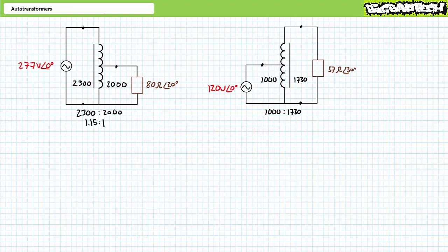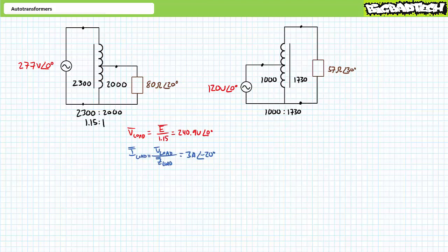Our first illustrated example features an autotransformer in a step-down configuration, where the larger primary input side has 2,300 turns, whereas the smaller secondary output side has only 2,000 turns. This autotransformer has a 2,300 to 2,000, or 1.15 to 1, turns ratio. The 277 volt primary input would be stepped down to roughly 240.9 volts. An application of Ohm's law demonstrates the load draws roughly 3 amps of current at an angle of negative 20 degrees.